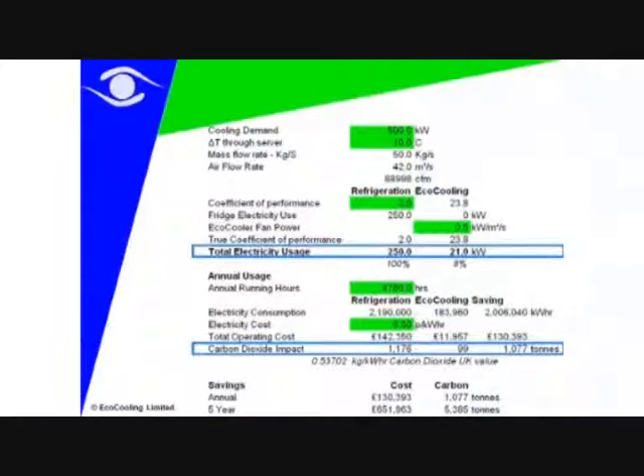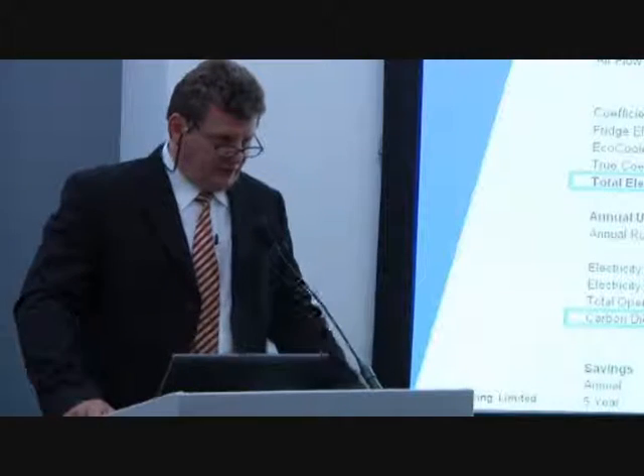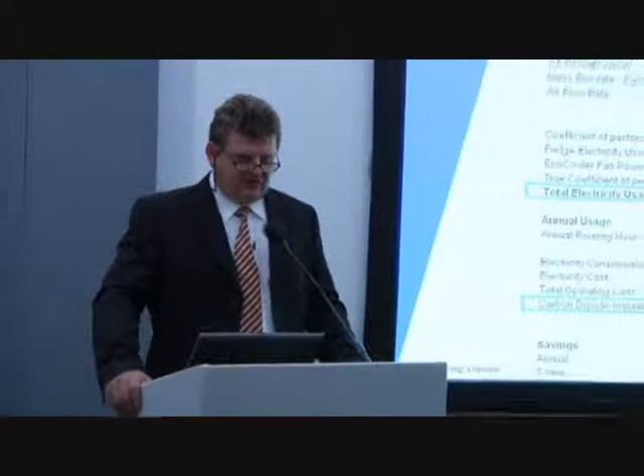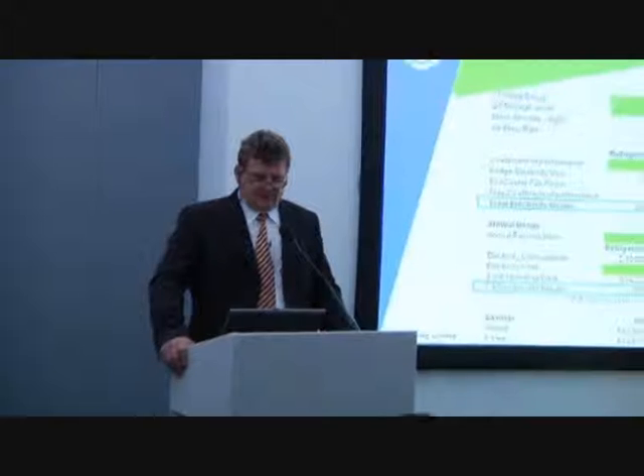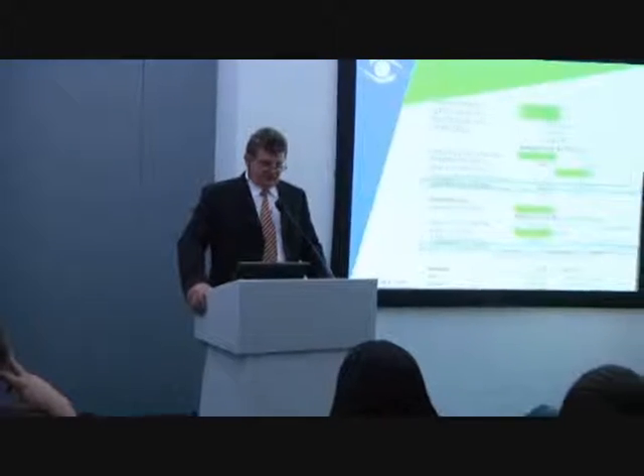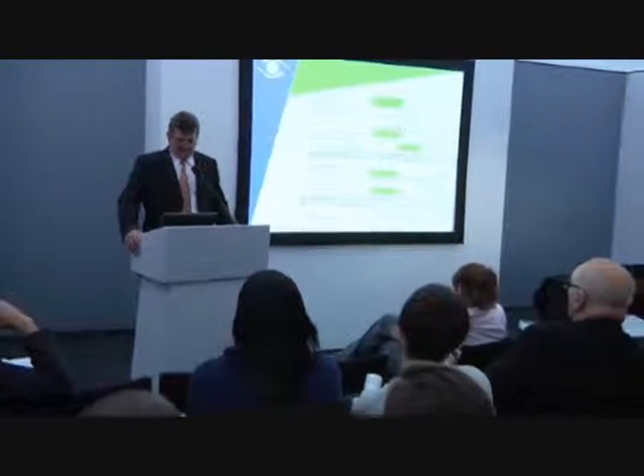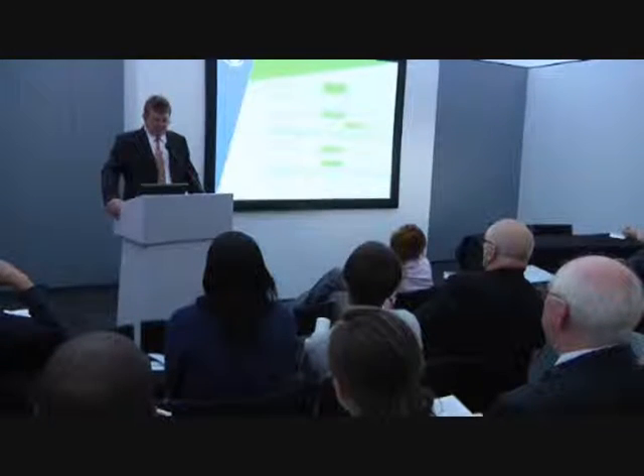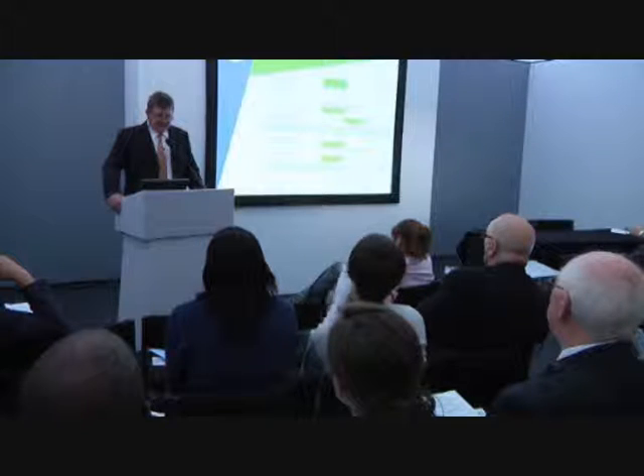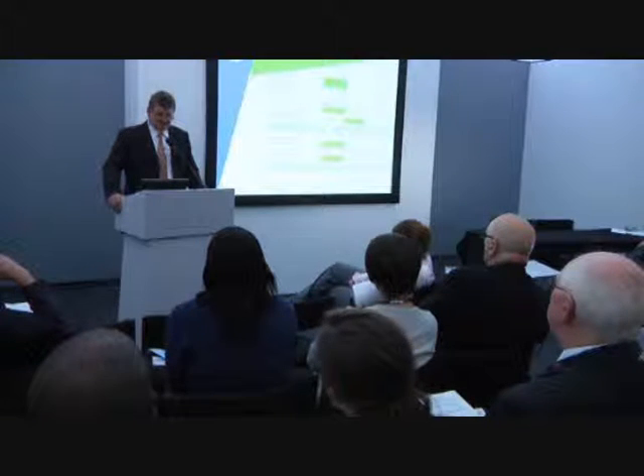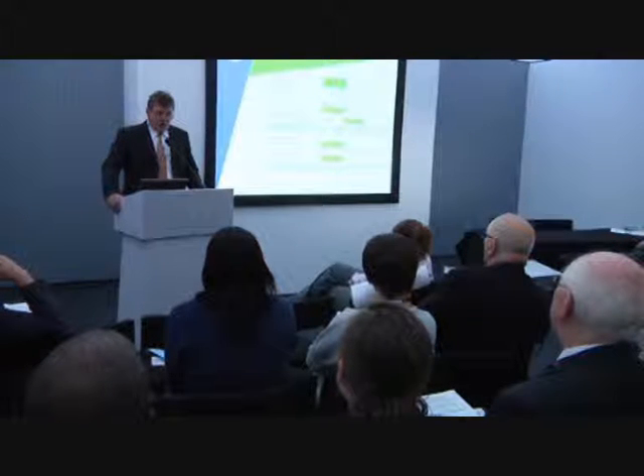Straight away, let's get to the numbers. Let's look at what we were trying to achieve at the planning stage with M247. As I said earlier, M247 is a 500 kilowatt, half megawatt data center. So on the lower third in terms of the size of data centers you would come across. When we look at a data center, a lot of people do get a little bit misled in that they concentrate a little bit too much on the actual cooling load. There's a little bit more to it than that. What we're actually trying to do is give all the servers the right volume of air. Wherever that air comes from is irrelevant, but you've got to give it the right volume. Now, 500 kilowatts of servers actually adds up to about 42 cubic meters per second of air. That's a lot of air. Where does it come from?